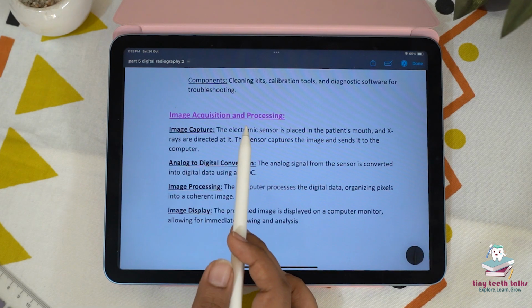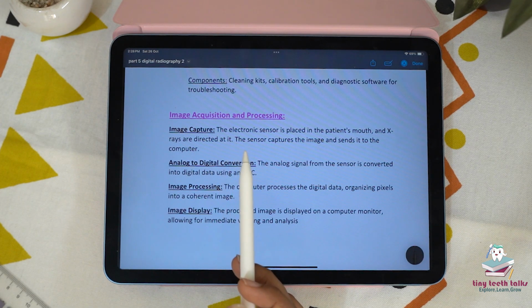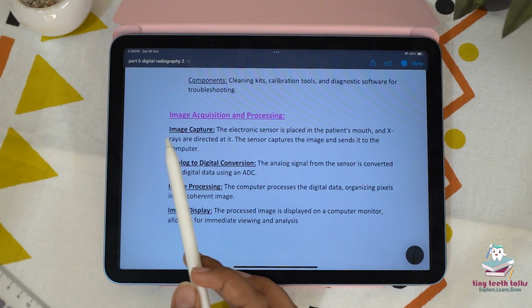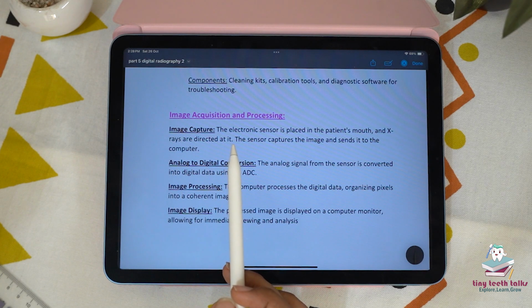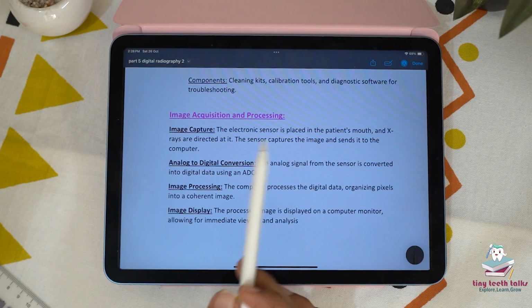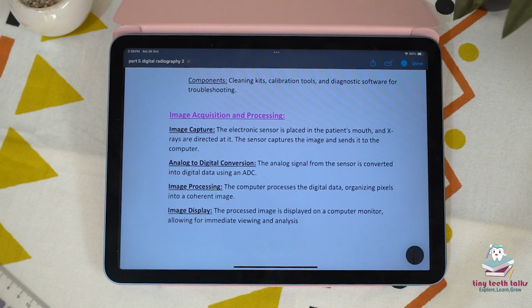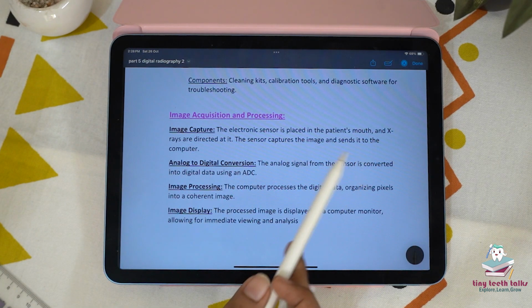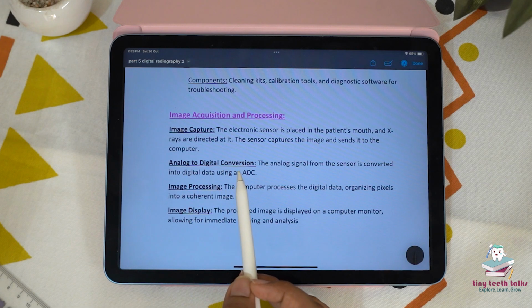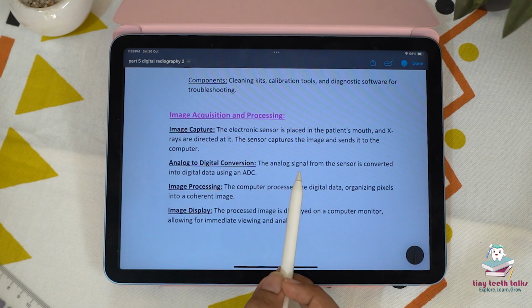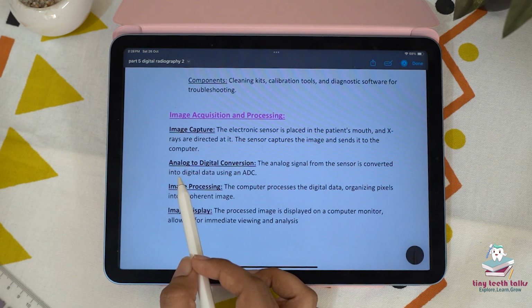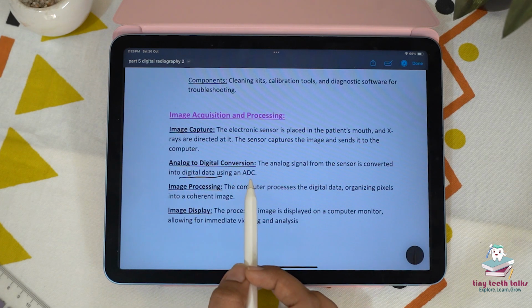Coming to the image acquisition and processing, which means how the RVG works. So first, image capture. The electronic sensor is placed in the patient's mouth and X-rays are directed at it. The sensor captures the image and sends it to the computer. Then analog to digital conversion. The analog signals from the sensor are converted into digital data using the analog to digital converter.